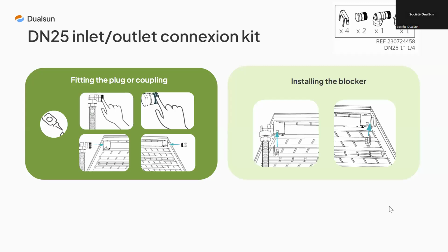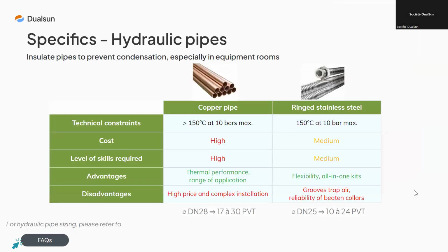Finally, here you can see, you can put grease on the O-rings and then insert those ones, and also the elbow fittings here and the final connections here to close the circuits. And so finally, we recommend using copper for the hydraulic pipes or ringed stainless steel, with the diameter of the pipe recommended here depending on the number of PVTs, on which the flow rate depends.